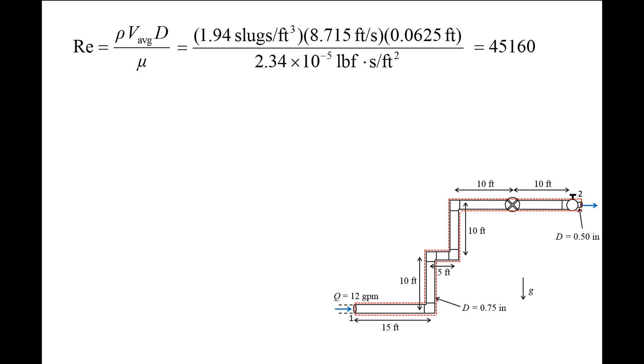Since the Reynolds number is greater than 4,000, this indicates the flow is turbulent and we must also calculate the relative roughness before finding the friction factor. Typical values of absolute roughness epsilon for new drawn tubing is 5 × 10^-6 feet. Dividing the roughness by the pipe diameter and converting inches to feet in the denominator, we obtain 8 × 10^-5 for the relative roughness.